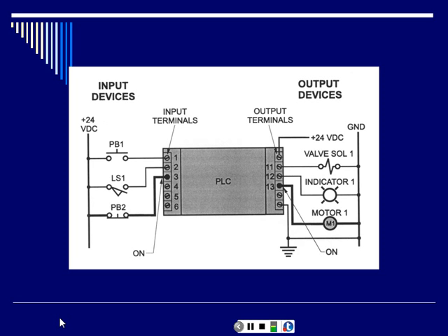And that's it. So what it's telling me here is this is not touched. I have power coming through here, and however they've done this, this one is programmed so that this motor turns on. But there's no physical link between that switch and that motor. It's done through programming. I really wish they would have put the little programming right there on top of the PLC so you could see the program. I might have to figure out what it is.